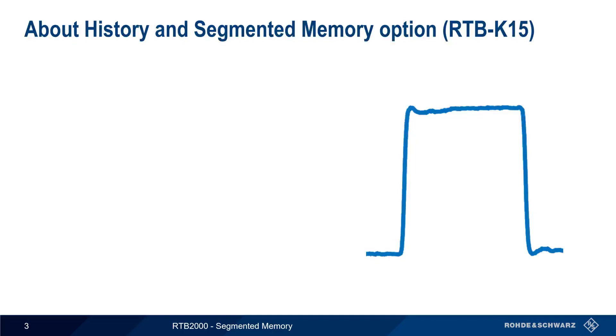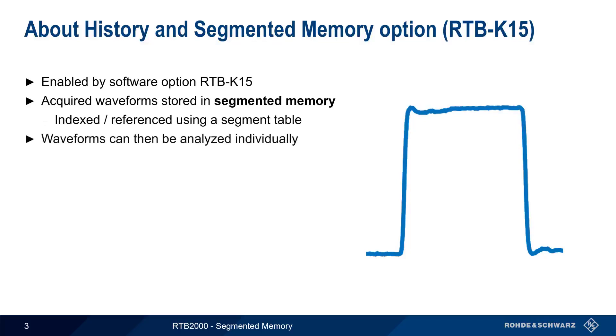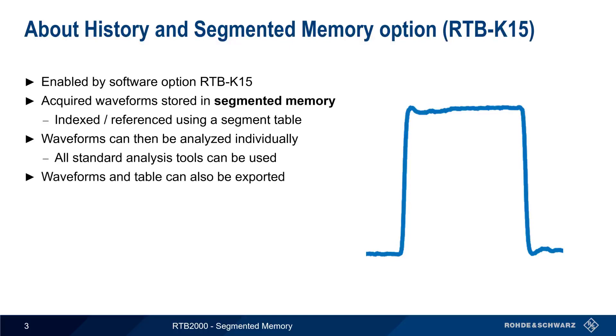Let's start with a high-level overview of history and segmented memory, which is enabled by the RTB K15 software option. This option allows acquired waveforms to be stored in so-called segmented memory. A segment table is used to index or reference these stored segments, and the stored waveforms can then be individually analyzed using all of the standard analysis tools available on the RTB. These waveforms and the associated table can also be exported for offline analysis or documentation, with both the waveforms and the table files in standard CSV format.